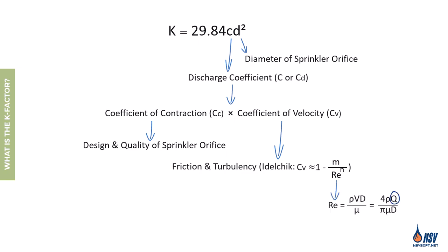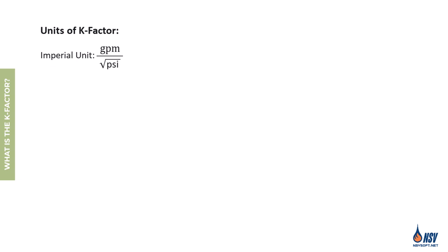The coefficient of velocity depends on factors such as friction between water and the internal surfaces of the sprinkler head and turbulence within the sprinkler. In theory, flow rate can influence the coefficient of velocity and thus the K factor. However, in fire sprinkler systems where the flow regime is highly turbulent, this influence is negligible. For hydraulic design we treat the K factor as constant, determined solely by the sprinkler's physical characteristics such as orifice size and manufacturing precision. In imperial units the K factor is expressed as gallons per minute per square root of psi.